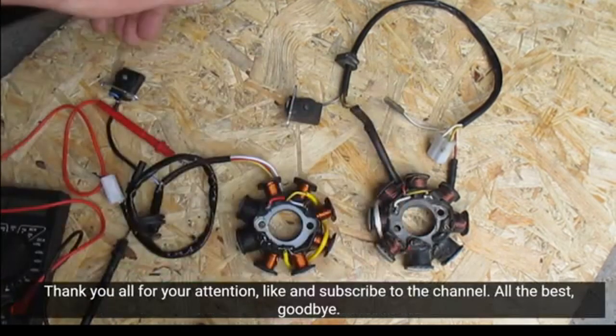Let's summarize. The reason for the generator malfunction is that all contacts go to ground. This means that some turn of the winding has burned out or become unusable. As you can see, the new generator stator does not hit ground.